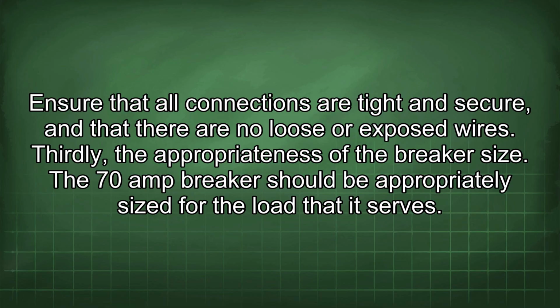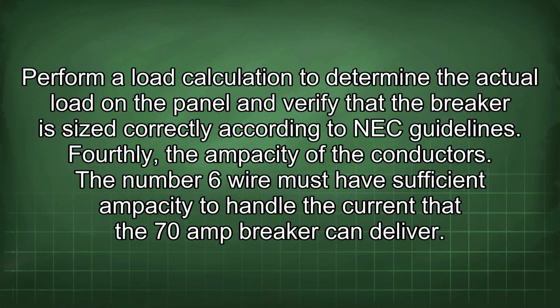Thirdly, the appropriateness of the breaker size. The 70-amp breaker should be appropriately sized for the load that it serves. Perform a load calculation to determine the actual load on the panel and verify that the breaker is sized correctly according to NEC guidelines.